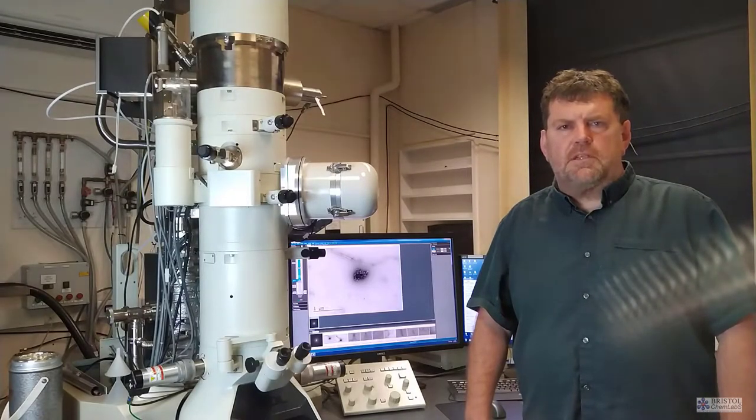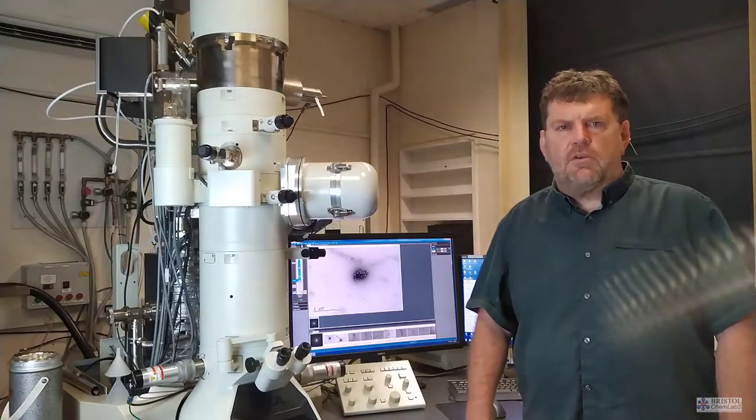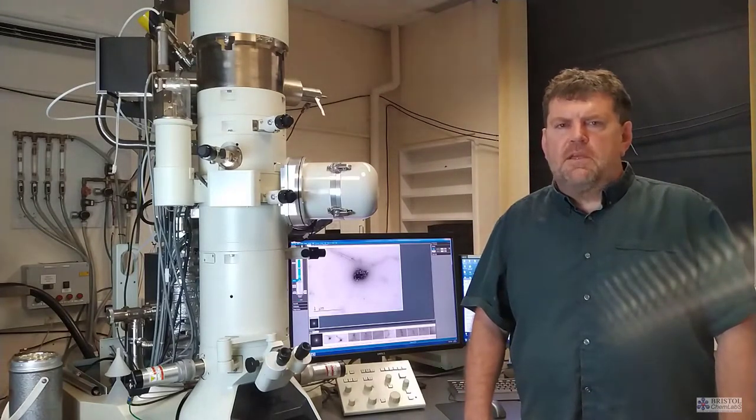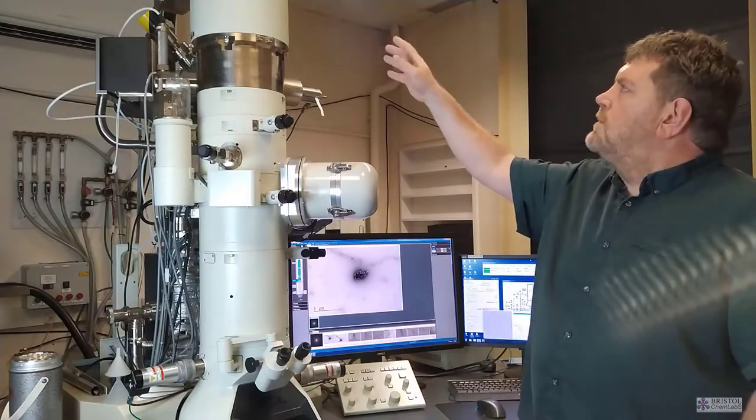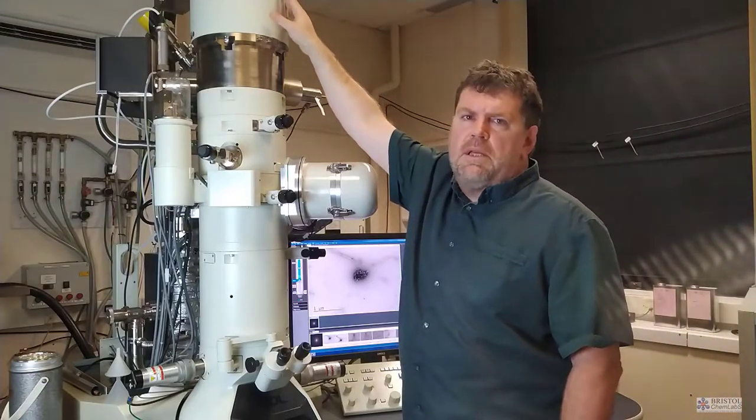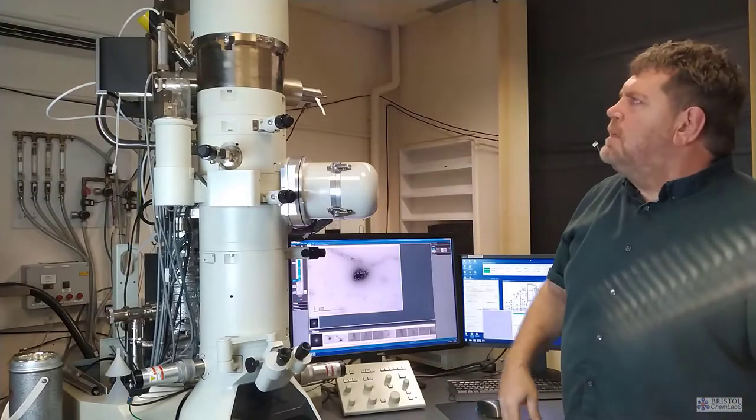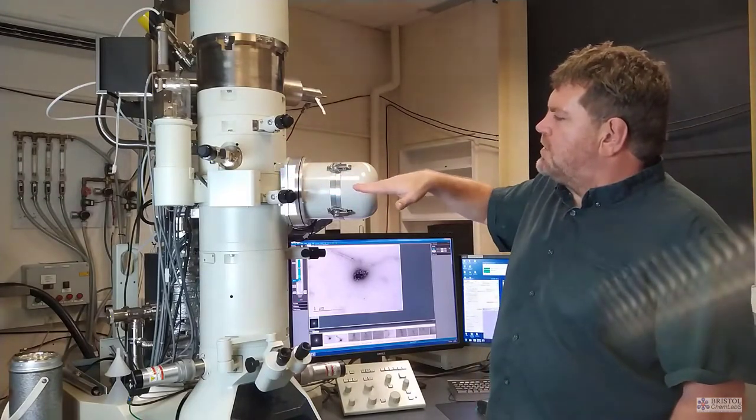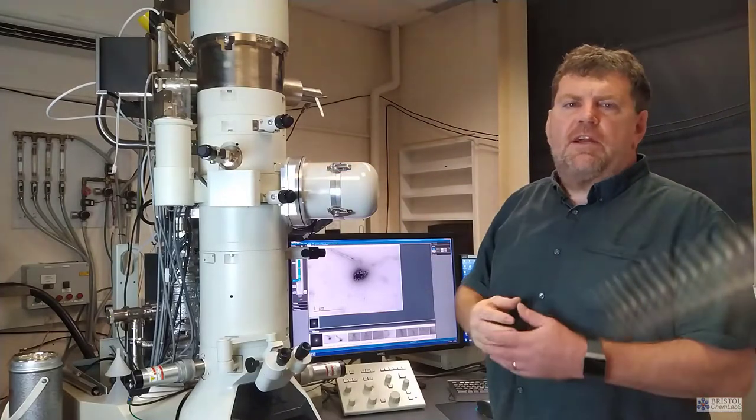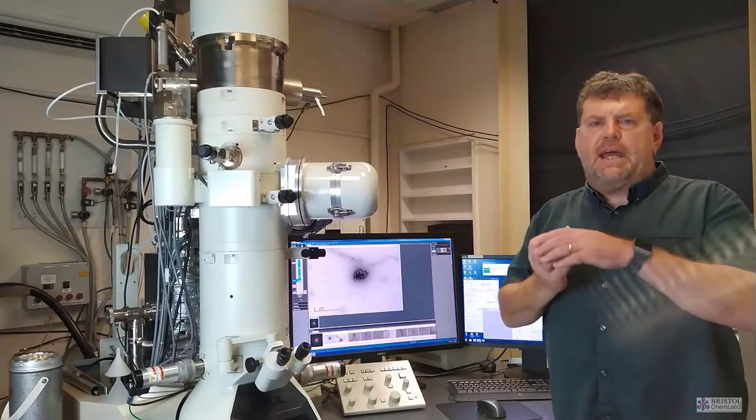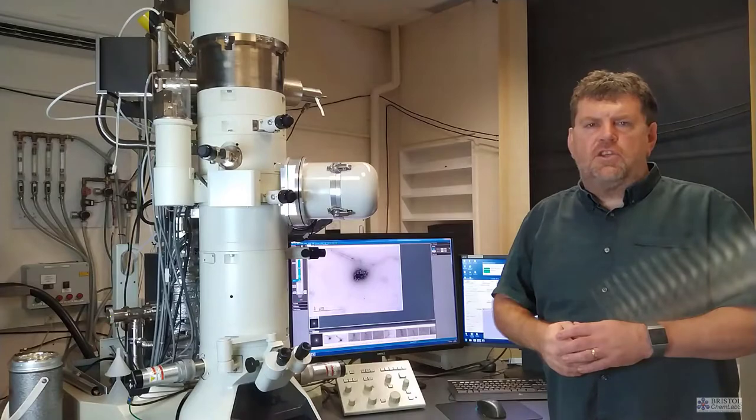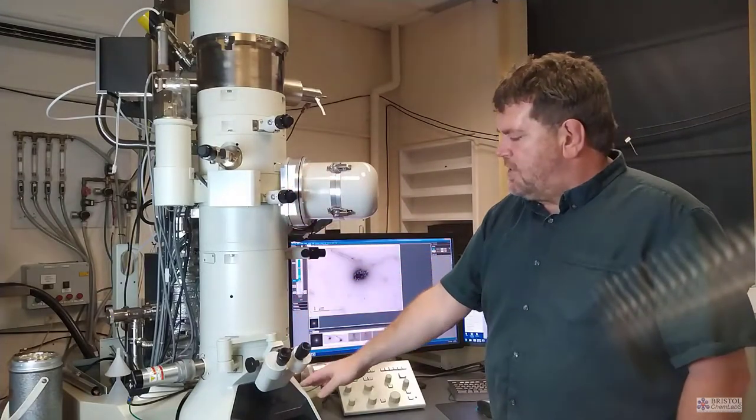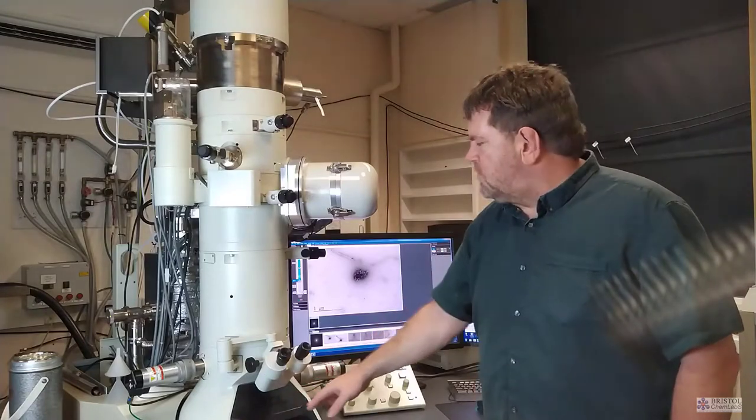There are two types of electron microscope: transmission electron microscopes and scanning electron microscopes. The scanning electron microscopes have got the simplest operation. The transmission electron microscopes have got the simplest design. It's very similar to an optical microscope. We have a source of illumination at the top, in this case a way of generating an electron beam. The electron beam is then fired down through the column of the microscope. And on this microscope, the sample actually goes in here. It's a transmission electron microscope, so we're trying to transmit that energy through the sample. And it's mainly used to look at the internal structure of materials. The electron beam passes through, interacts with the sample, and that allows an image to be generated or projected onto a screen or onto a display.